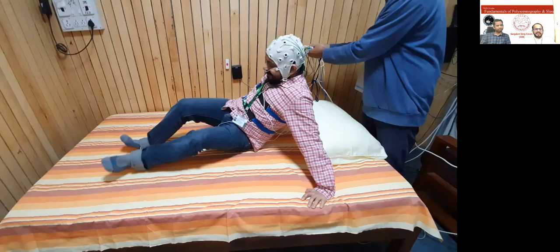What will we do when the subject wants to go to the toilet at night? Good question and good concern as well. That's why we use a junction box. As you can see in the video, all these electrodes are connected to a junction box, and from the junction box, it goes to the amplifier. When the subject wants to go for a washroom break, we disconnect the junction box, and the subject can carry it, go to the washroom, come back and connect it back. So we don't have to plug in all the electrodes again in the middle of the night.